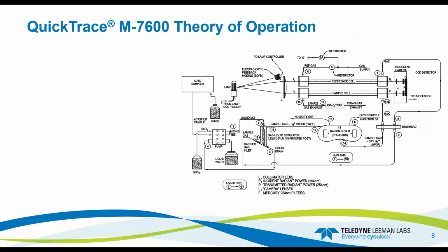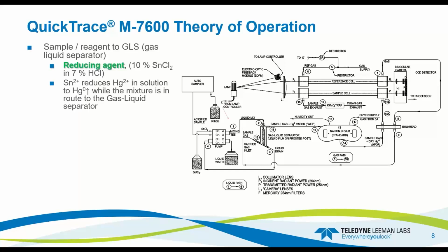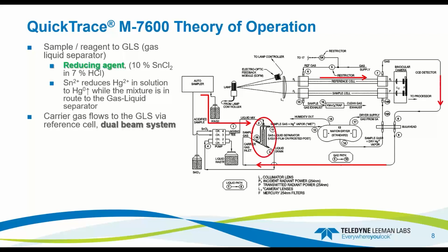So here's basically how the system works. It's a dual cell system. We have a reference cell and sample cell. Our stannous chloride is 10% and 7% HCl. The stannous is going to reduce the sample, which is digested, oxidized to Hg2+, in solution on its way to the gas liquid separator. So by the time it gets there, it's already going to be Hg0.